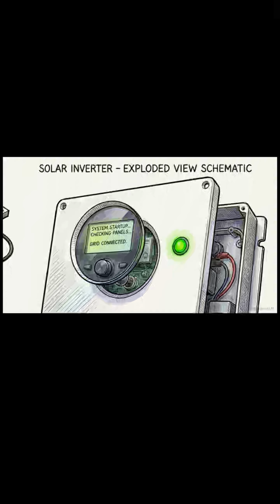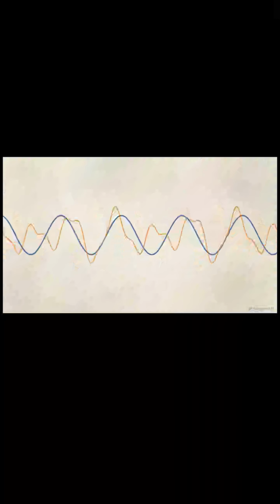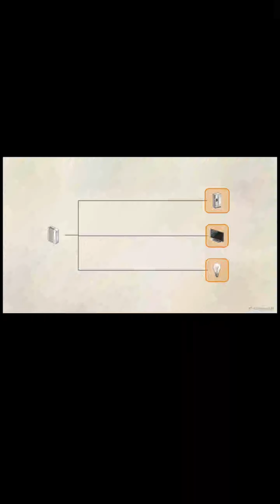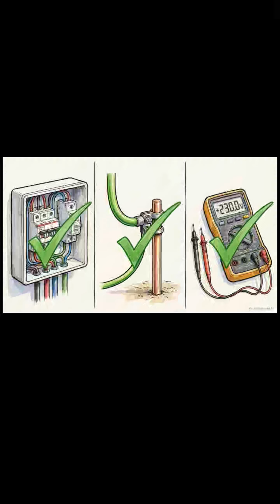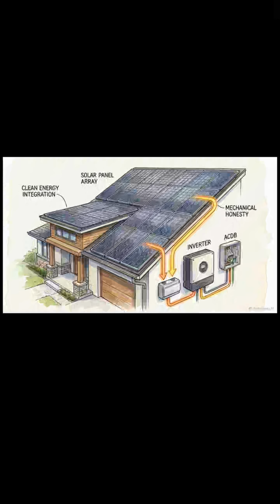You will hear the inverter click as its screen wakes up. It runs a brief diagnostic check to synchronize with the grid's frequency, and then it begins actively pushing solar power into the home. Sticking strictly to this exact order of wiring, dual earthing, and polarity testing ensures you leave behind a compliant, safe, and fully operational single-phase solar system.